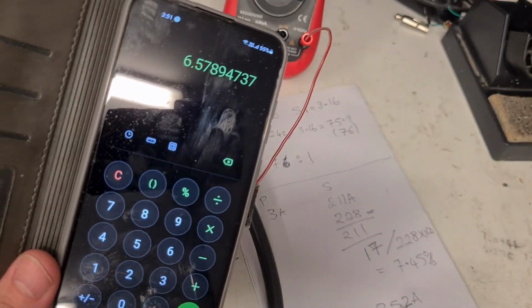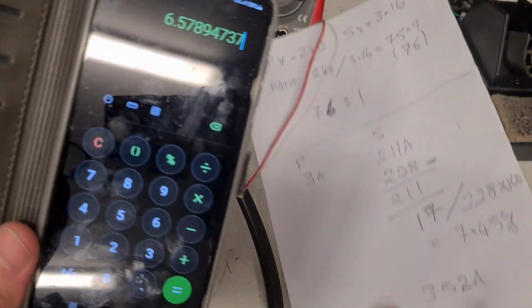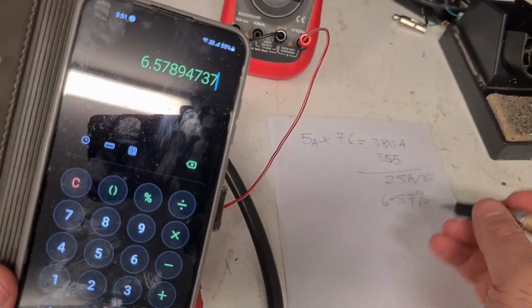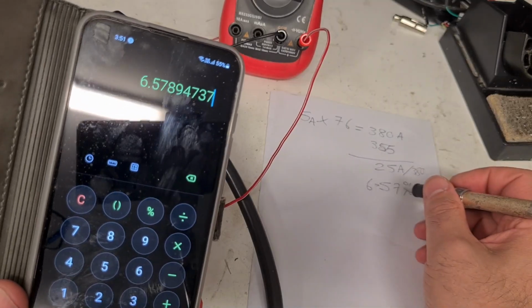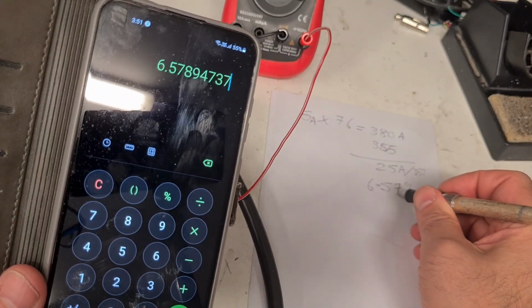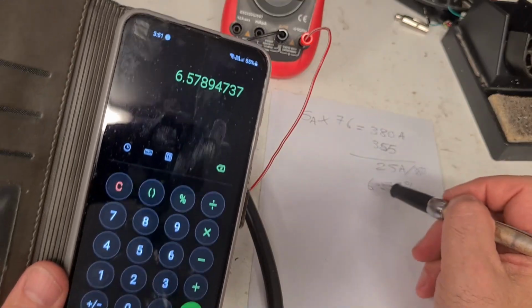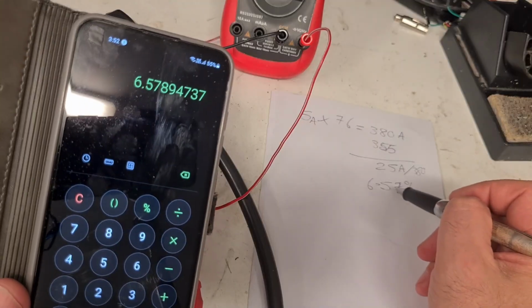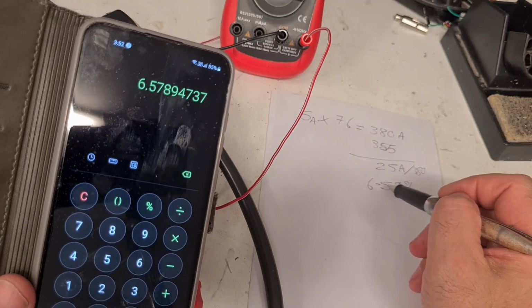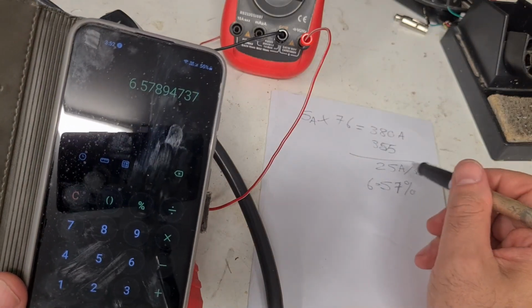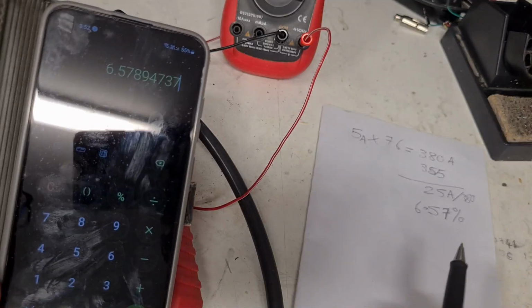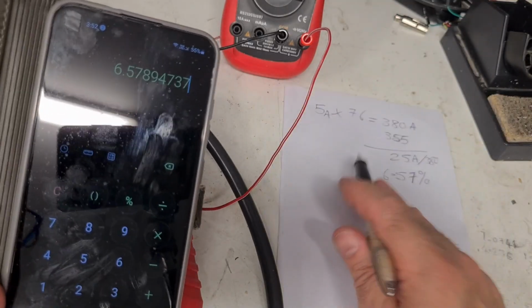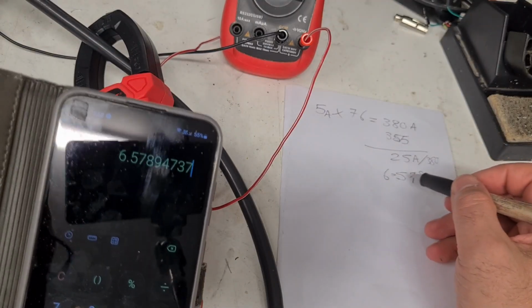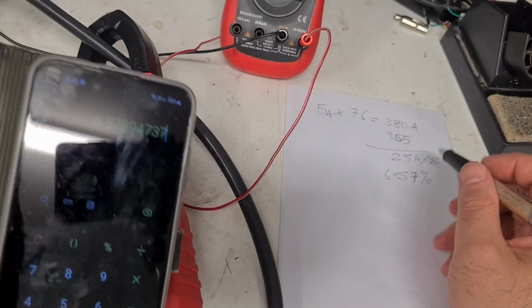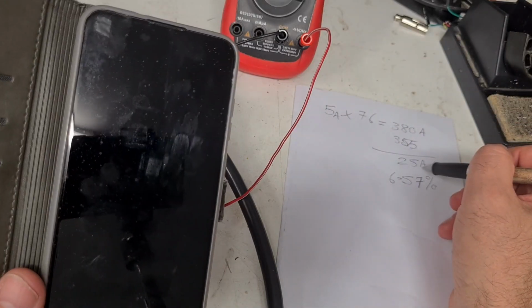Before it was 7. So at the lower current it was 7.45. The higher I'm going with the current, the more efficient the secondary is becoming. So the shunts, looks like to me, are more effective at a lower current. At a higher current, the shunts are becoming less effective. Okay, so let's see. Almost 1% less. 1% less effective. Which tells you that's not a lot. I am not losing a lot by the shunts because we're only talking about 25 amps less at 5 amps on the primary.